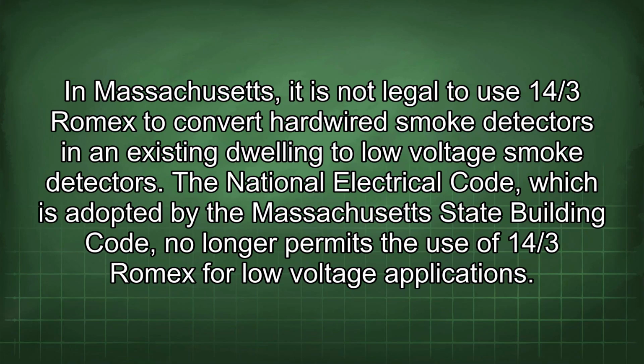In Massachusetts, it is not legal to use 14/3 Romex to convert hardwired smoke detectors in an existing dwelling to low-voltage smoke detectors. The National Electrical Code, which is adopted by the Massachusetts State Building Code, no longer permits the use of 14/3 Romex for low-voltage applications.